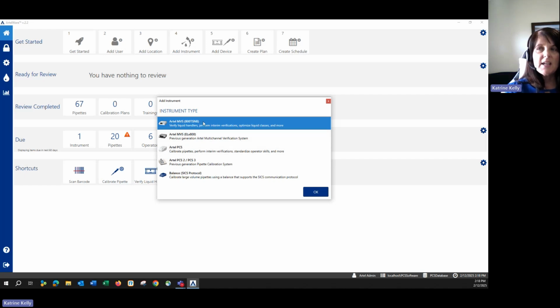If you are using the MVS, it does utilize the same software program, so you can add in your MVS instrument as well. And as I mentioned, if you are connecting the software to a balance for volumes greater than 5 mLs, you would add your balance to the software here. As long as the balance has a SICS protocol, it will communicate with the software. Most of the newer balances that have come out in the last 10 or so years are compatible with that SICS protocol.